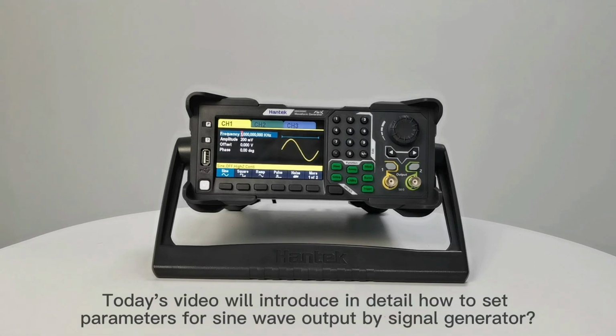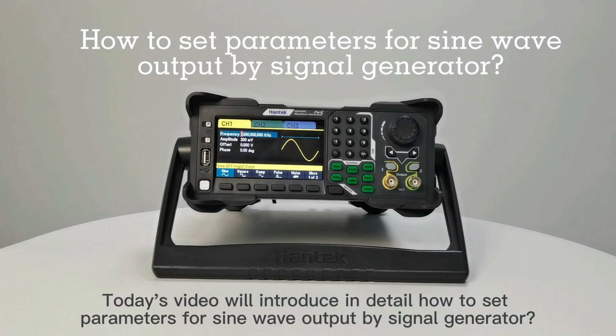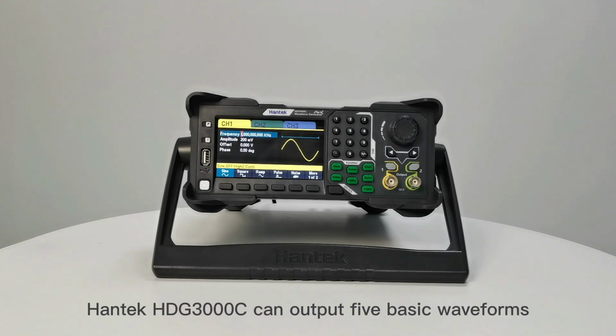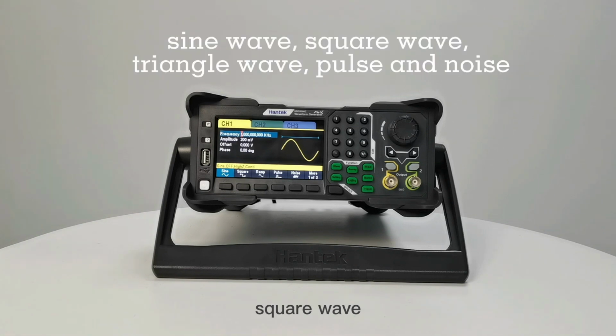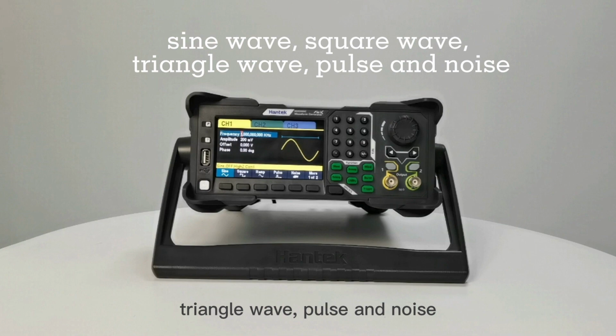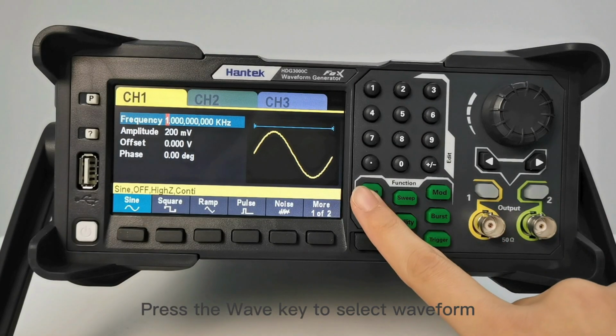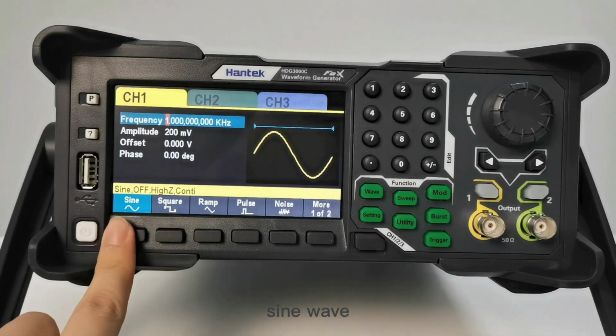Today's video will introduce in detail how to set parameters for sine wave output by the signal generator. The HDG3000 can output 5 basic waveforms, including sine wave, square wave, triangle wave, pulse and noise. Press the Wave key to select the waveform, and choose sine wave.